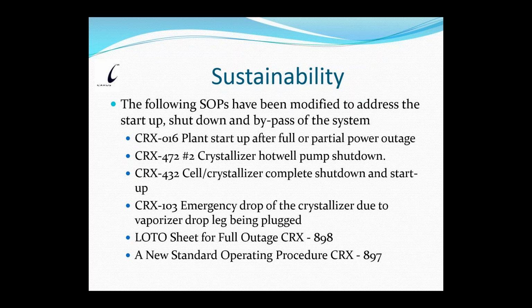And our lockout tagout documents are all picture related. So we'll actually take a picture of the pump or the valve or whatever and then state what needs to be done, and then they sign off on it and then do the verification that it doesn't start, etc.